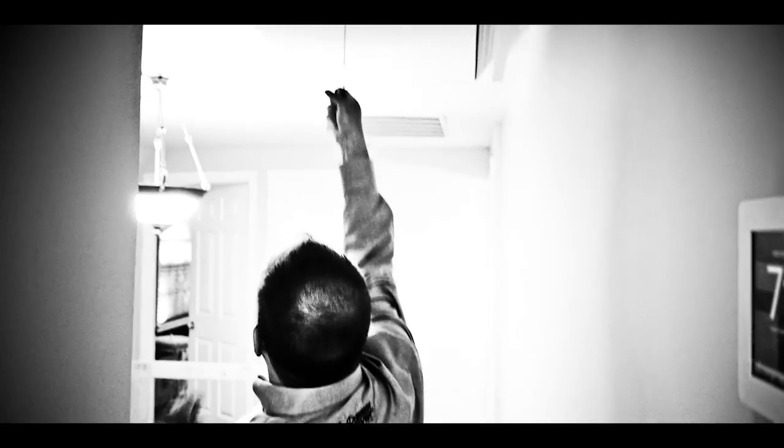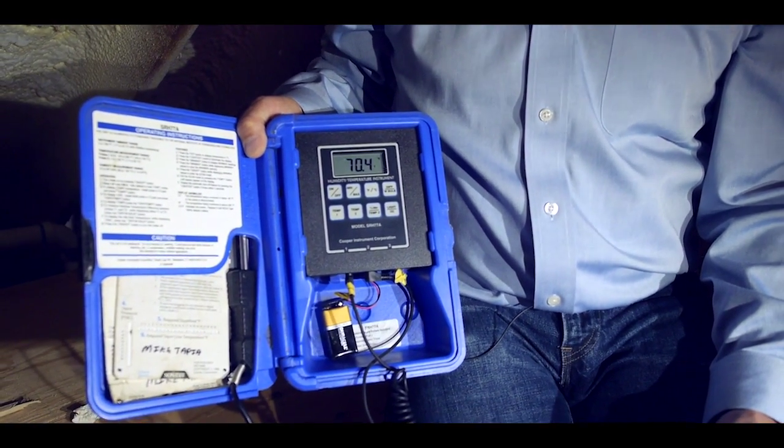The air conditioning system is located in the attic. You have a 125-degree temperature up there and you've got to get it down to 70. It takes a while for that system to start operating, and it's using a lot of energy. But now if the attic is part of the conditioned space of the home and the system is essentially sitting inside the home, it only has to start off at 80 degrees and drop 10 degrees — a big difference. Wow, you won't believe it. It's 95 degrees outside and we're up here in the attic and it is 70 degrees. The air conditioning system hasn't even come on yet. The attic is perfectly comfortable — I could stay up here all day.